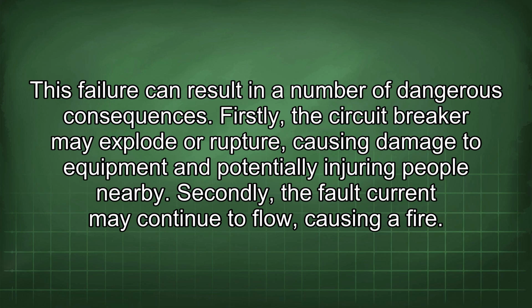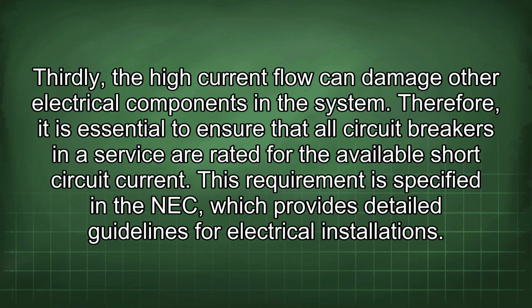Firstly, the circuit breaker may explode or rupture, causing damage to equipment and potentially injuring people nearby. Secondly, the fault current may continue to flow, causing a fire. Thirdly, the high current flow can damage other electrical components in the system. Therefore, it is essential to ensure that all circuit breakers in a service are rated for the available short circuit current. This requirement is specified in the NEC, which provides detailed guidelines for electrical installations.